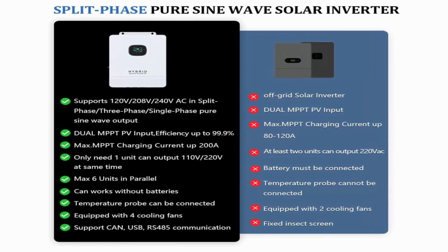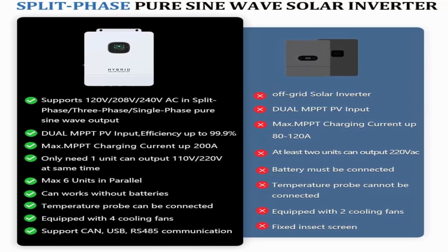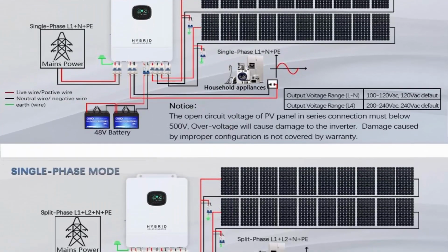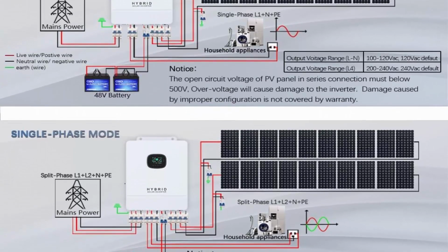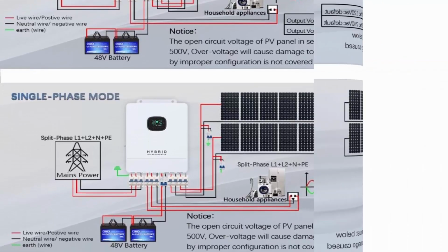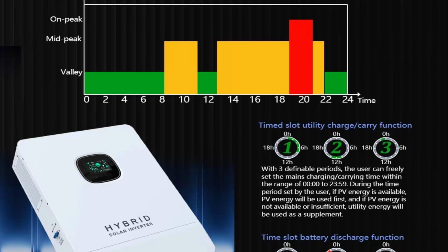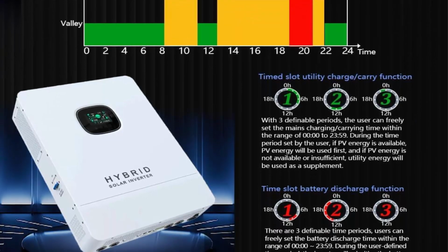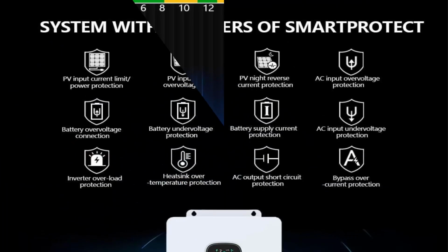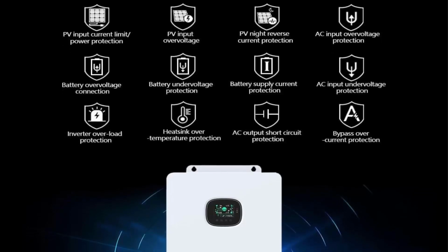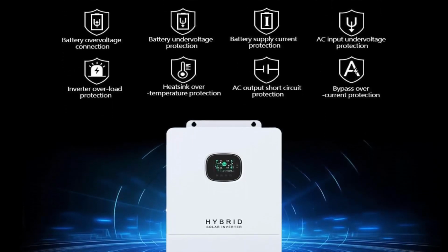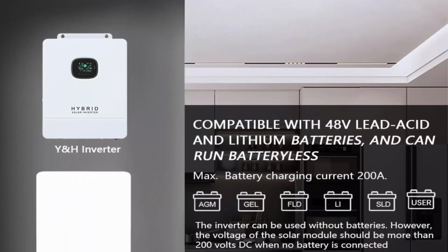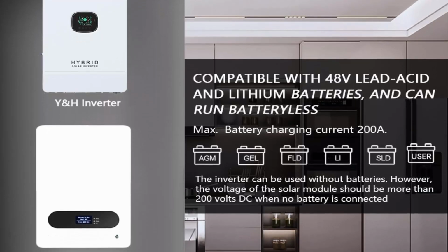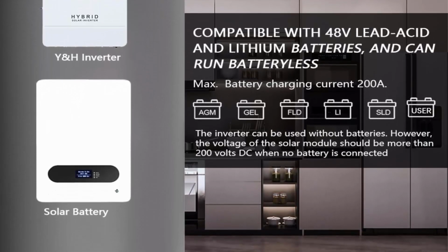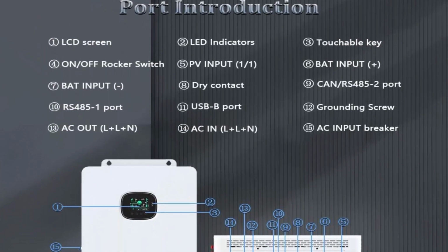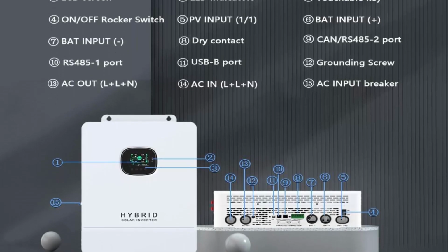This upgraded solar hybrid inverter supports parallel connection, rated output power 10,000 watts, maximum peak power 20,000 watts, rated output voltage AC 120 volt and 240 volt, split phase and single phase, battery voltage, 48 volt DC, built-in 200A MPPT solar charging, maximum PV input power 11,000 watt, voltage range 125-425 volt DC, maximum open circuit voltage VOC 500 volt DC, startup voltage 130 volt, PV cable specification, 10 AWG, maximum charging current 200A, nominal input frequency, 50 and 60 Hz, supports CAN, USB, and RS-485 communication.